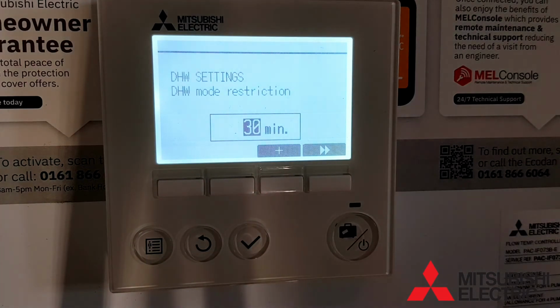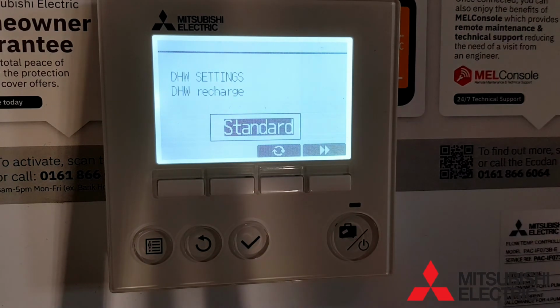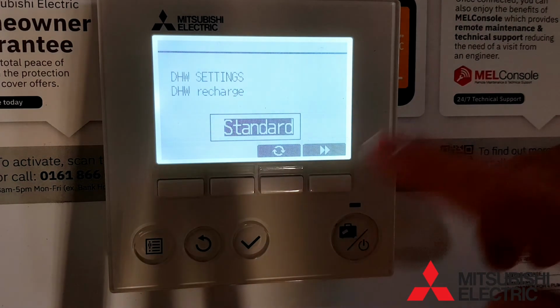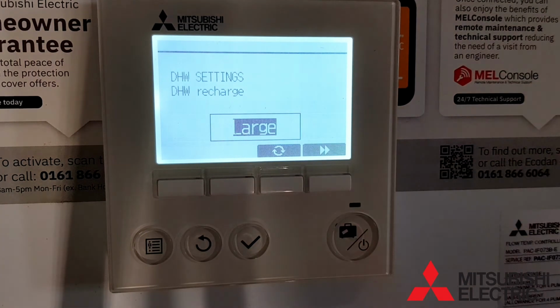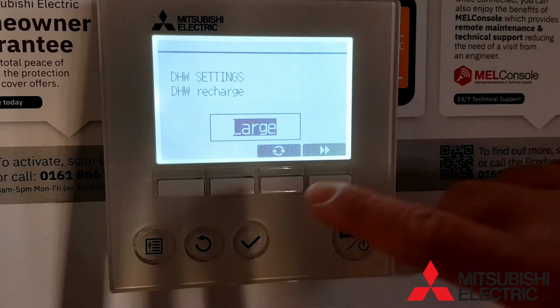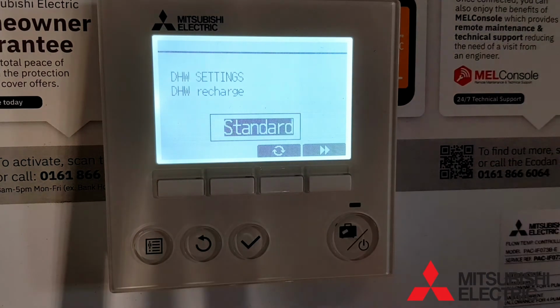Next, we have a new function for the FTC 6, the domestic hot water recharge function. As the FTC 6 has a temperature probe at the top of the cylinder and an additional sensor at the bottom of the cylinder, there will be a temperature difference between the two readings. When set as standard, the system cycles on and off using the top sensor. When you have a larger cylinder and a larger water content, it is recommended to set the function to large, so it cycles on and off from the bottom sensor.